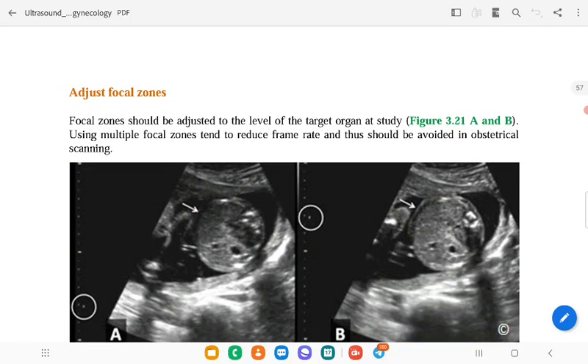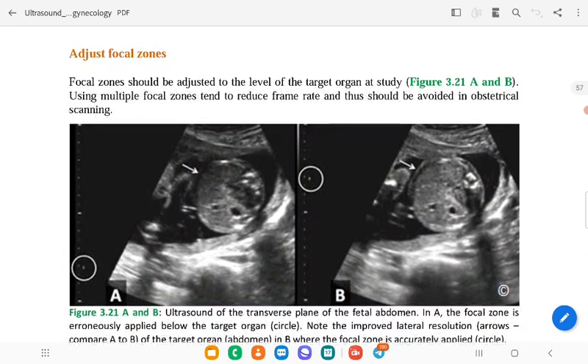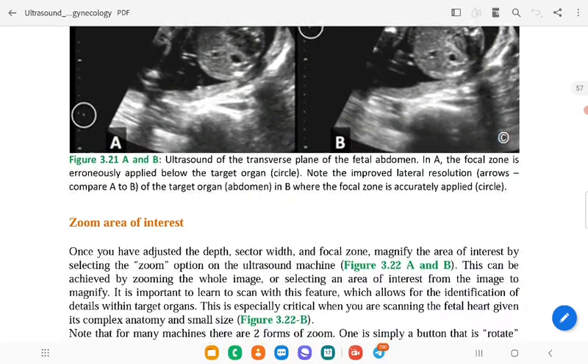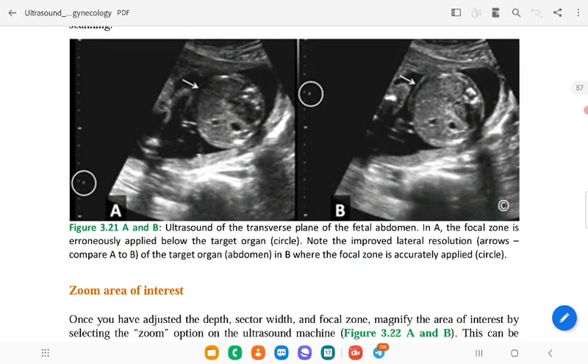Adjust focal zones. The focal zones should be adjusted to the level of the target of the study. Using multiple focal zones tends to reduce the frame rate, and this should be avoided in obstetrical scanning. The ultrasound of the transverse plane of the fetal abdomen, in which a focal zone is erroneously applied below the target organ. Note that improved lateral resolution is seen when comparing A and B, where the focal zone is at the target organ.